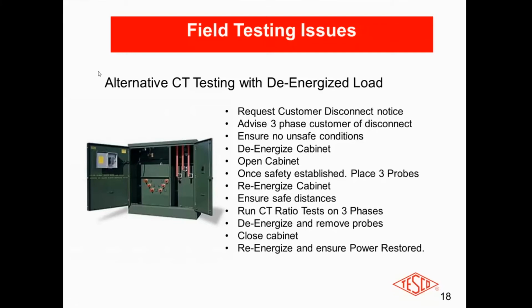Again, it may be once every few years, but nonetheless, the procedure would be to ensure no unsafe conditions and then de-energize the cabinet. And then with the approach again and making sure there's no arc flash in there, you're opening up a cabinet. You've got to be careful when you open it up, all the oxygen's suddenly flying in there. So once they've established that, they can put the probes on. They then will back away and then re-energize the cabinet. Then they do the testing.